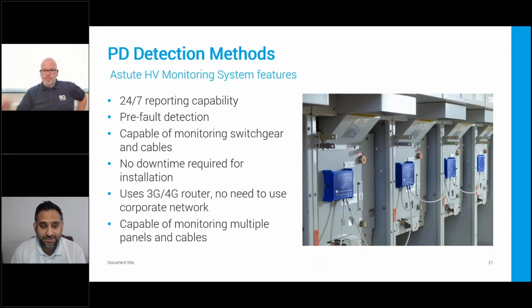It essentially is a 24/7 monitoring system. It's a modular system, so it allows you to install individual nodes and individual sensors around the switchgear, around the different components of the switchgear, as well as cables. Just like with all the other PD equipment, it's non-intrusive, so you don't really need to have an outage to install any of this equipment. You can install the Astute monitoring system while the equipment is still in service.